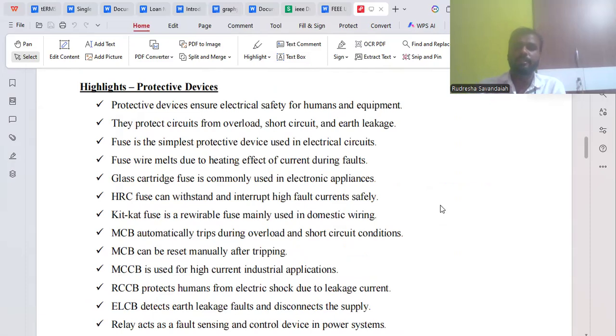Highlight the protective devices. Protective devices ensure electrical safety for humans and equipment. They protect the circuit from overload, short circuit, and earth leakage. Fuse is the simplest protective device used in electrical circuits. Fuse wire melts due to the heating effect of current during faults. A glass cartridge fuse is commonly used in electronic appliances. HRC fuse can safely interrupt high fault current. Kit kat fuse is a rewirable fuse mainly used in domestic wiring.